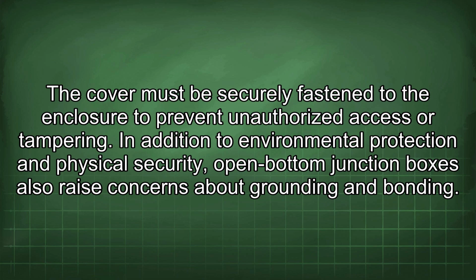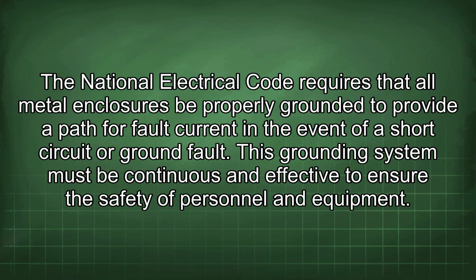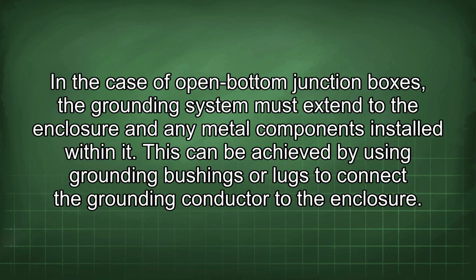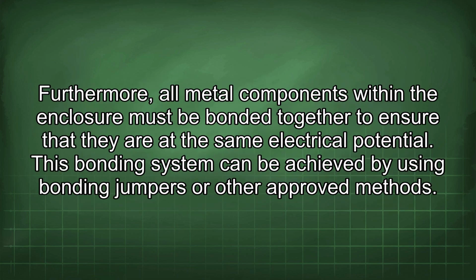In addition to environmental protection and physical security, open bottom junction boxes also raise concerns about grounding and bonding. The National Electrical Code requires that all metal enclosures be properly grounded to provide a path for fault current in the event of a short circuit or ground fault. This grounding system must be continuous and effective to ensure the safety of personnel and equipment. In the case of open bottom junction boxes, the grounding system must extend to the enclosure and any metal components installed within it. This can be achieved by using grounding bushings or lugs to connect the grounding conductor to the enclosure. Furthermore, all metal components within the enclosure must be bonded together to ensure that they are at the same electrical potential. This bonding system can be achieved by using bonding jumpers or other approved methods.